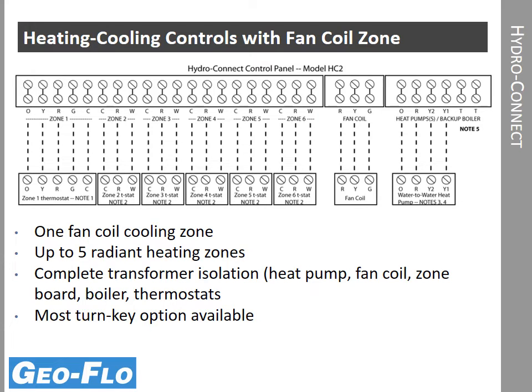The simplest panel, like I mentioned, the most limiting, but certainly simplest from an installation standpoint, has complete transformer isolation. So this is the 1 fan coil cooling zone. It would be typical of a home with 1 fan coil that is ducted for the cooling in the home, and then up to 5 radiant heating zones. So with this setup, we still have zone 1 as our master thermostat, and that also handles cooling, and then all of the other zones are heating only radiant zones. So the customer always knows exactly how the system operates. 1 thermostat for cooling and the other thermostats for heating. And also there's not a need to have to manually switch over the system at the mechanical room. That zone 1 thermostat tells the buffer tank controls whether it's in heating or cooling. So it makes certainly the most turnkey option available.